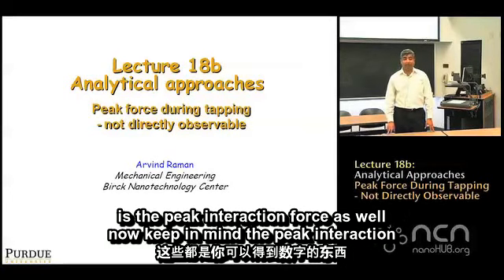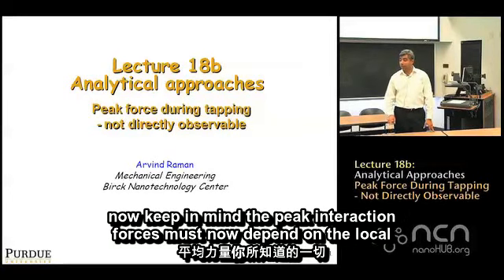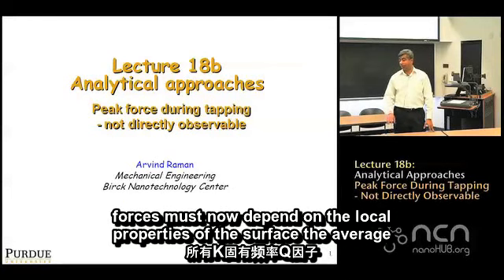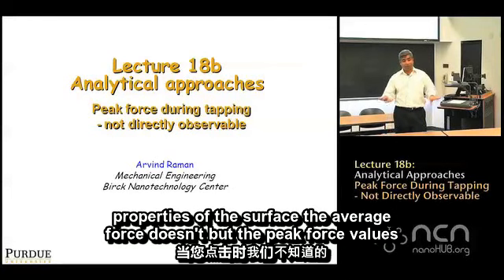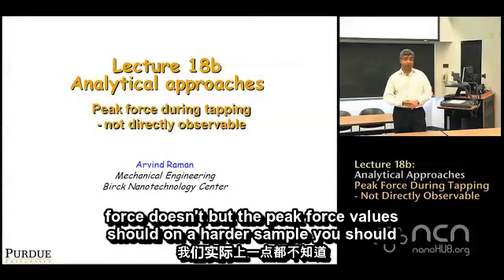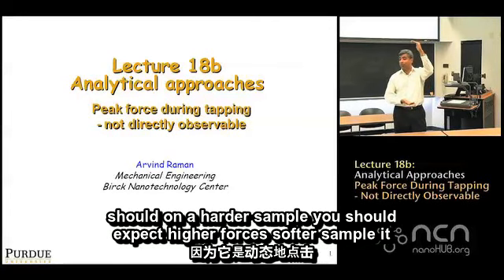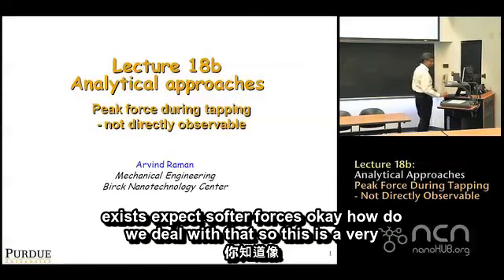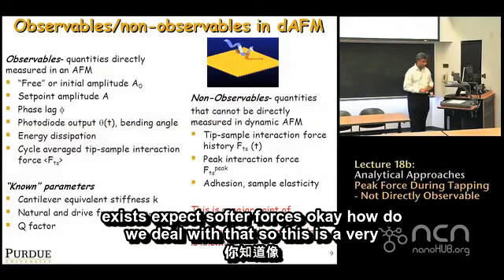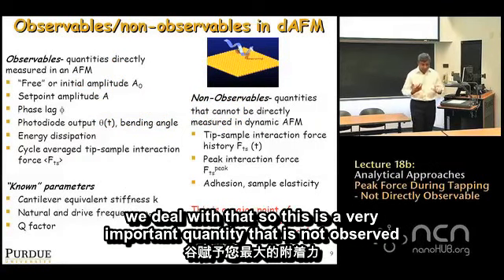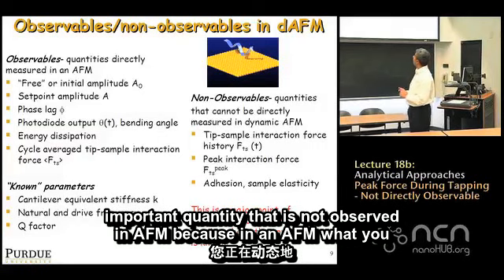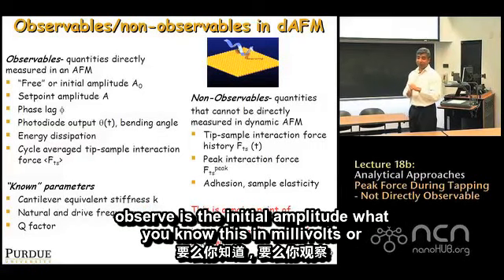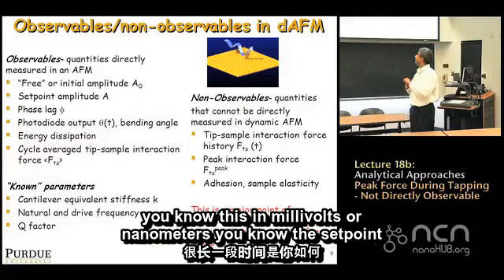Peak interaction forces must depend on the local properties of the surface — the average force doesn't, but the peak force value should. On a harder sample you should expect higher forces; on a softer sample, softer forces. In AFM, what you observe is the initial amplitude in millivolts or nanometers, the set point amplitude, and the phase lag as you scan a sample.